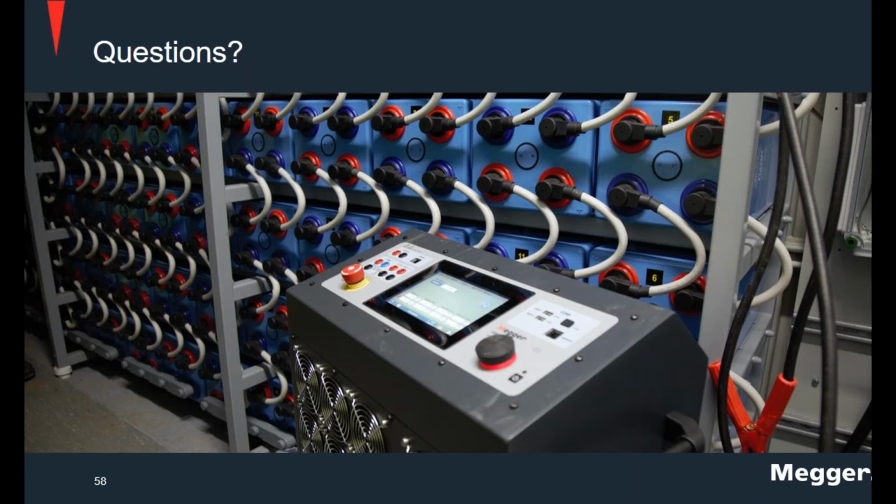All right, thanks, Daniel. Sanket, does load test reduce the lifespan of the battery? Is a discharge test considered destructive testing? So Volney did touch upon this during his presentation. There is this misconception that the load test reduces the lifespan of the battery, but if you think about it, a battery is manufactured to last for 100 discharge cycles at least.